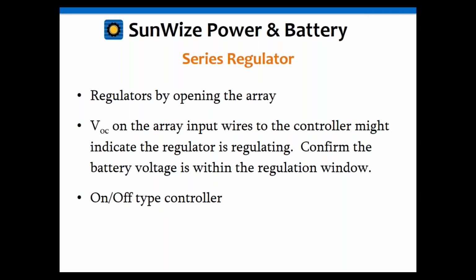On a series regulator, the regulator actually functions opposite. It regulates by opening the array. Now, this is also an on-off type, but the difference is, if it opens the array to regulate, then instead of the array voltage being 0, the array voltage is going to be the open circuit voltage. So for a 12-volt system, that voltage should be around 20 to 22 volts. For a 24-volt system, between 40 and 44. So if you see your array voltage is that, and your battery voltage is within that window I mentioned earlier, somewhere between 14.1 volts and 13.8, then your battery is probably in regulation.